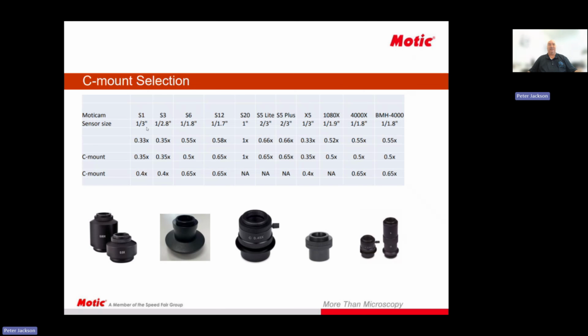So if we look at the sensor size, if we pick this one here, the S1, it's got a 1/3 sensor size. So we recommend a C mount that we call a 0.35x, or you could use a 0.4x C mount to use that sensor, and so on. So when we quote you a microscope and a camera, we'll quote the appropriate C mount that is suitable to fit both the camera and the microscope. As I said, it's very rare to be able to mount our cameras onto other vendors' microscopes.